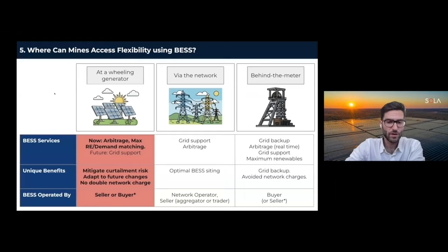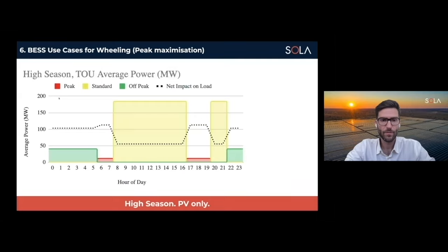There are some unique benefits to co-location of BESS. You mitigate the curtailment risk associated with those generators. So if you've got a solar plant that is generating in the daytime, and there's a big surplus of solar on the network, you can mitigate that risk. There are potentially network charge benefits that arise from the way that the batteries are used. And the battery can potentially be operated by either the buyer or the seller.